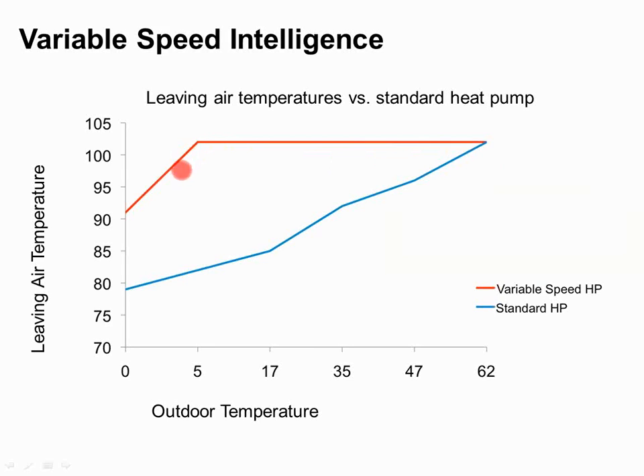And that's where you see over here on the left, in this particular example at 5 degrees, my discharge air temperature starts dropping off even on the variable speed, because I have to speed up that indoor blower to get the BTUs I want. But in this particular heat pump example, everything above 5 degrees outside, I can make sure that nobody gets that cold blow scenario. When it drops below 5 degrees, somebody's going to have to help me out. That means an electric strip heater or a gas furnace or something like that.